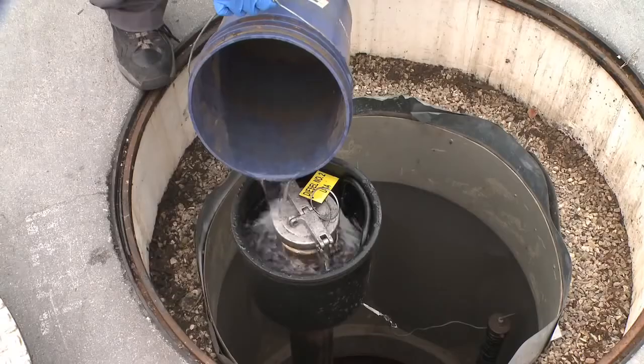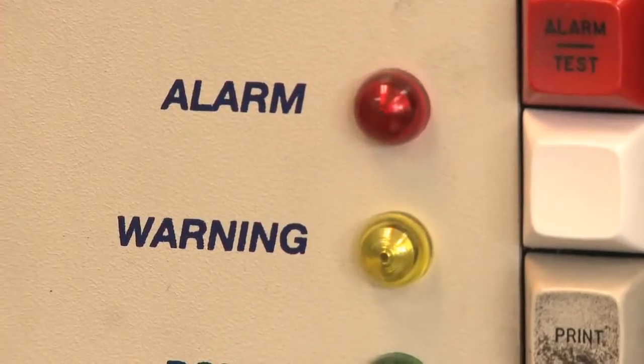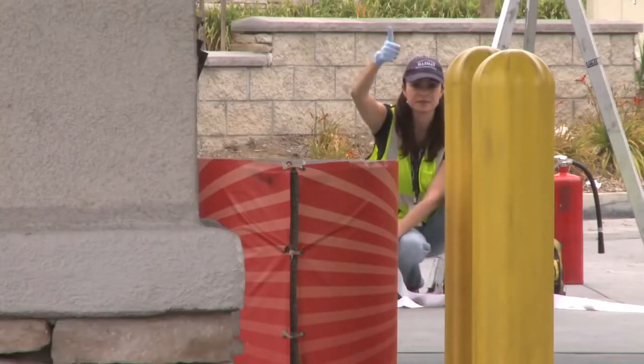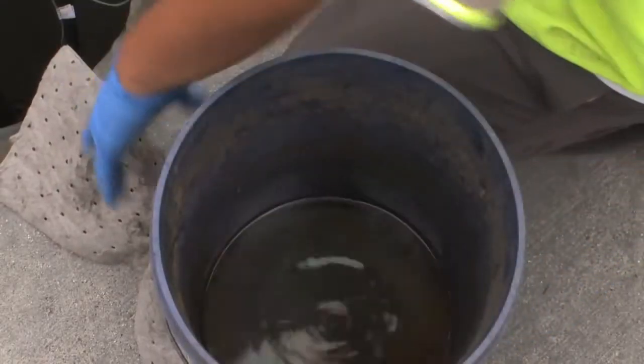Dip in water — to pretend the sensor came into contact with water — then we have to see the alarm in the monitoring system. And we do that for every single sensor; it's a repetitive process. The vibration from the pump lets her know if it's on or off, and she communicates this with a thumbs up or thumbs down. It's all part of her job to keep the environment safe.